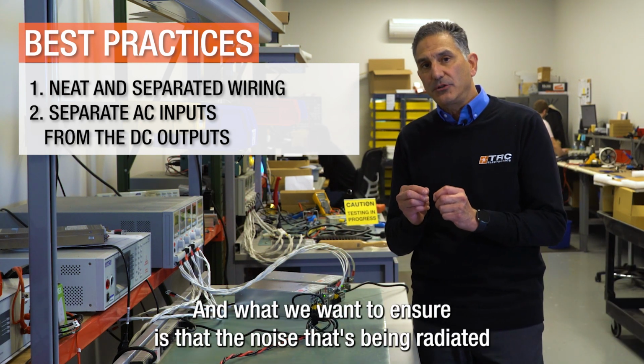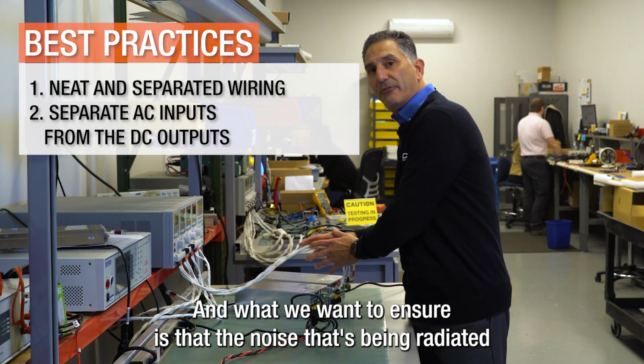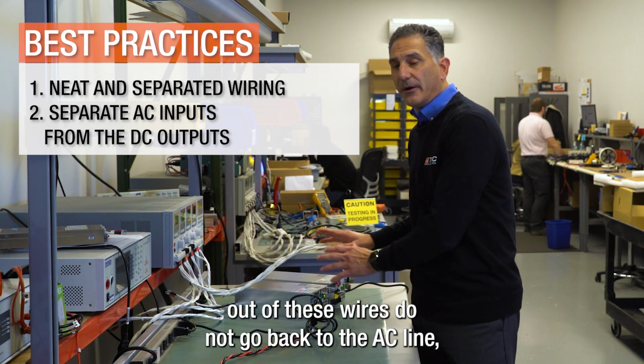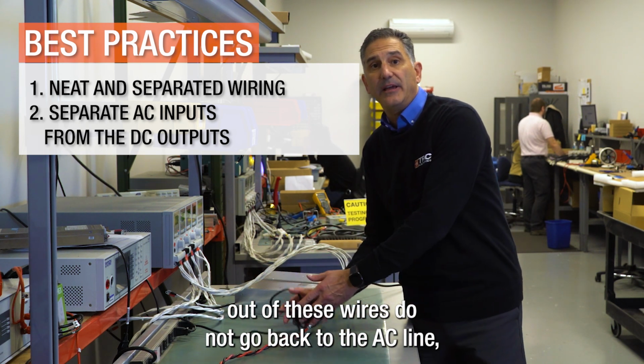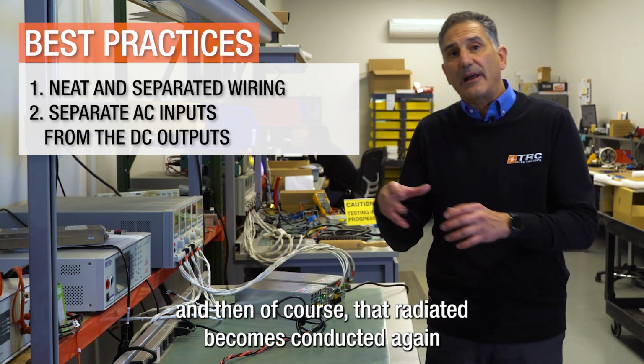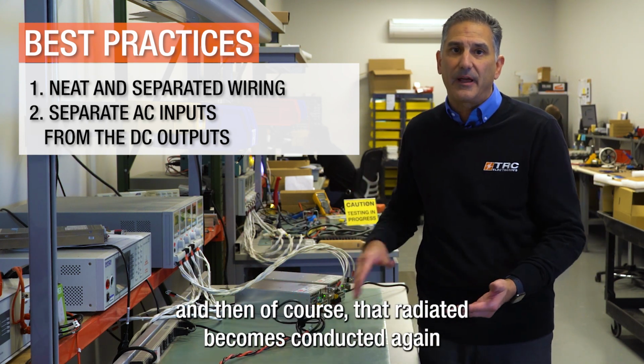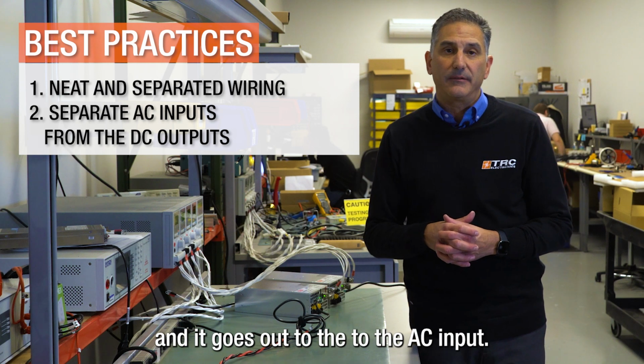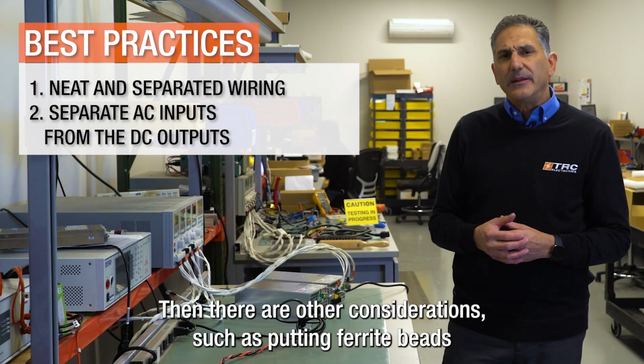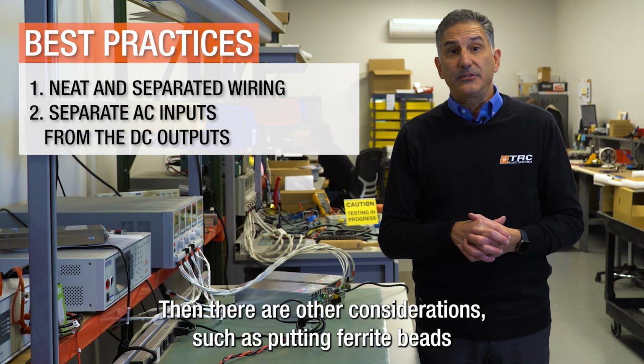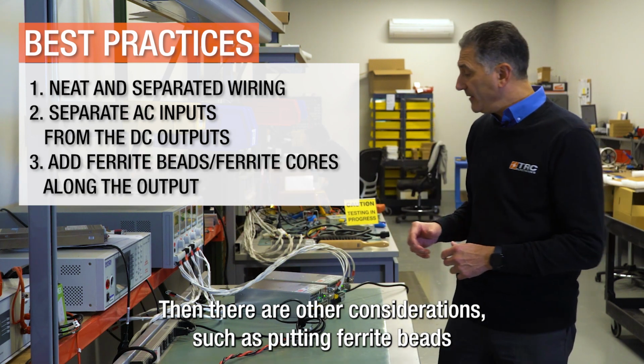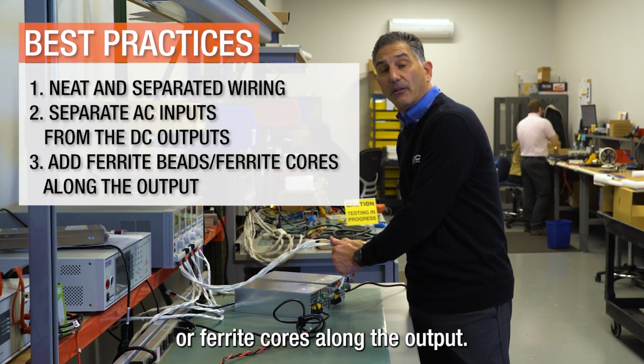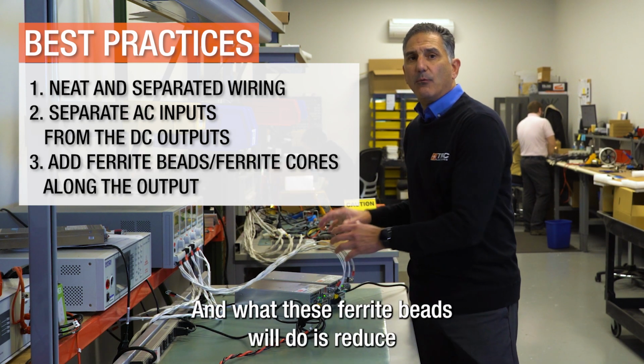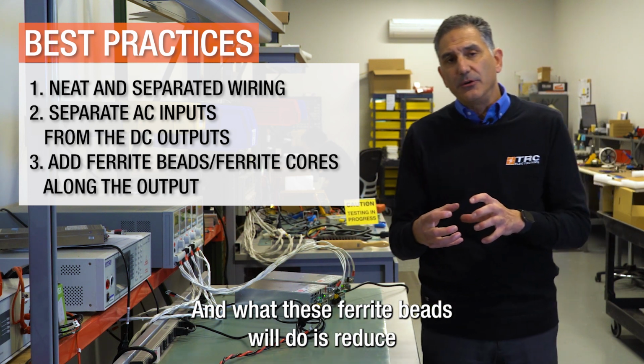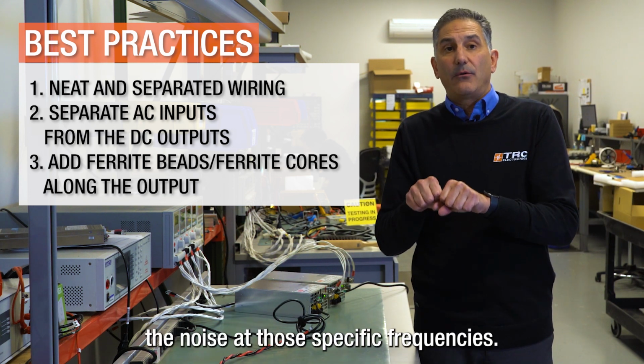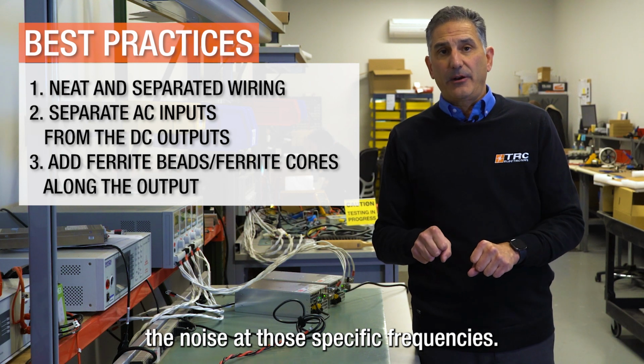What we want to ensure is that the noise being radiated out of these wires does not go back to the AC line, and then of course that radiated noise becomes conducted again and goes out to the AC input. Then there are other considerations, such as putting ferrite beads or ferrite cores along the output. What these ferrite beads will do is reduce the noise at those specific frequencies.